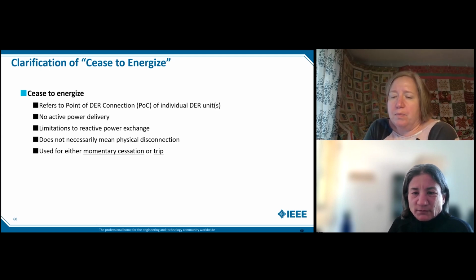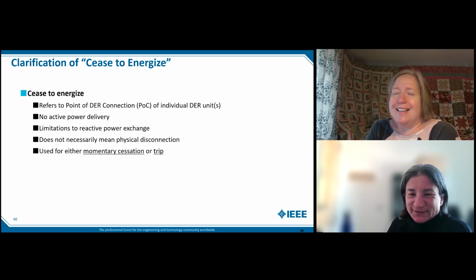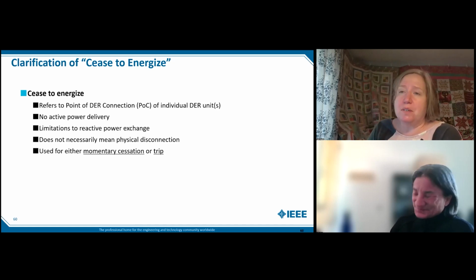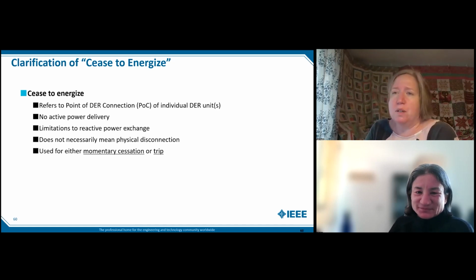As I mentioned, we are a high user of hotline blocking. All of our new switchgear comes with the line VTs already installed. We do employ transfer trip. And this is where I will do the plug for IEEE 1547.2. Can you remind us what that one is? That is the application guide for IEEE 1547 2018. It's IEEE 1547.2 2023. There's a lot of really good information in there.